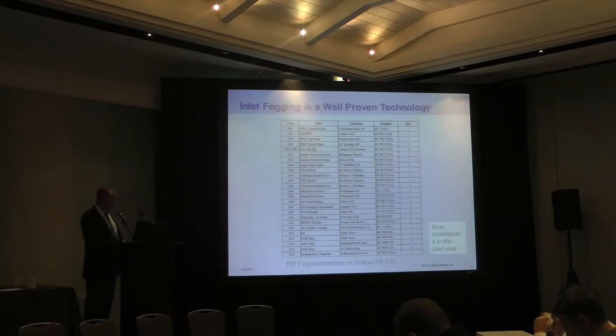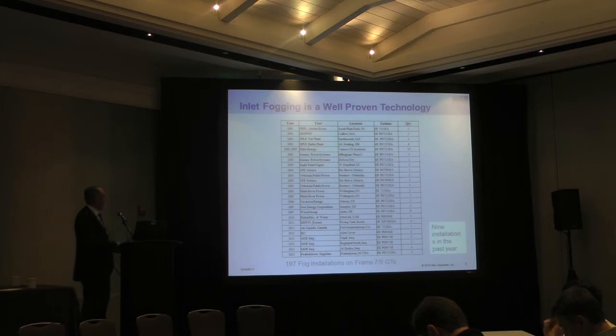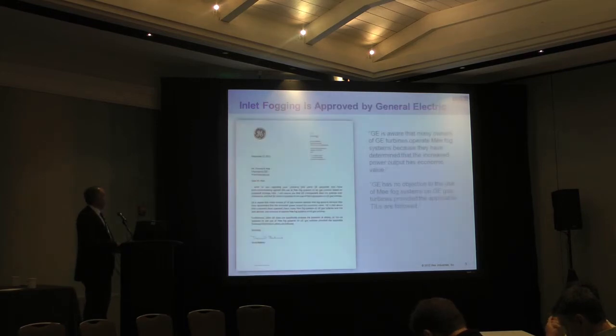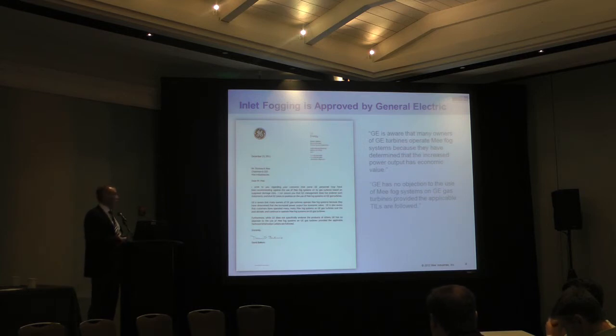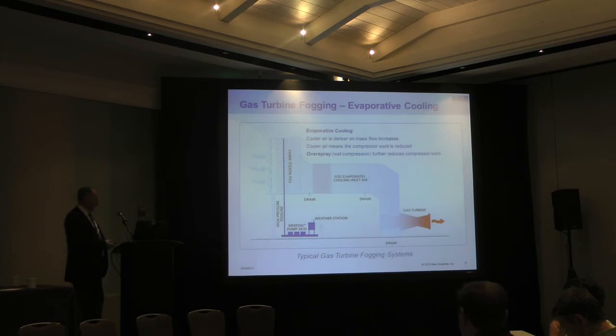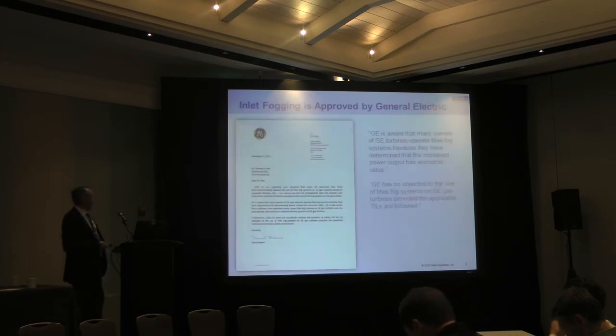So we've also done 9 installations in the past year, so it continues to be a fairly popular technology. And the new news in inlet fogging is that GE has recently approved the use of at least MEFOG systems on their gas turbines. So they gave us this letter showing that they approved of the technology.